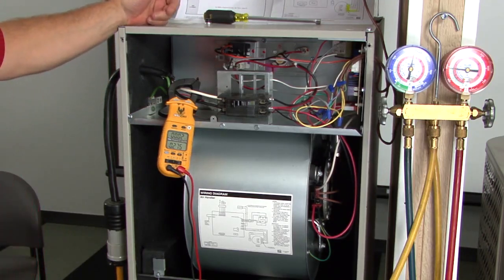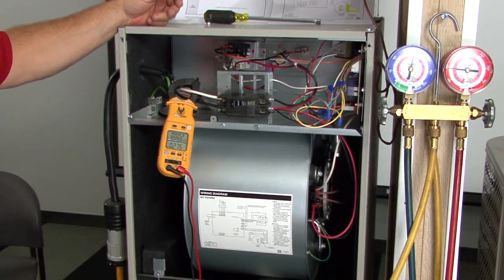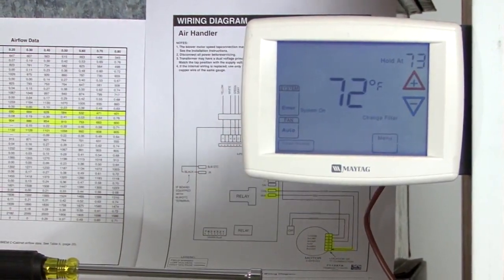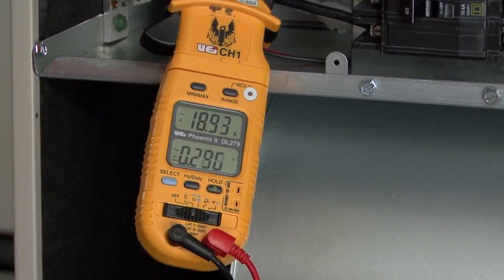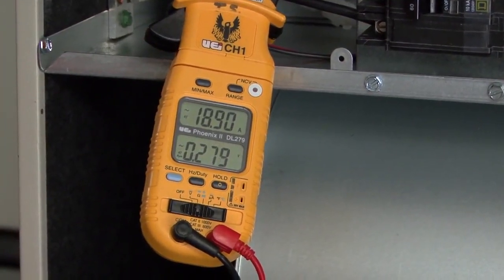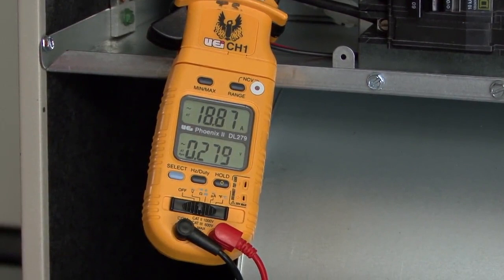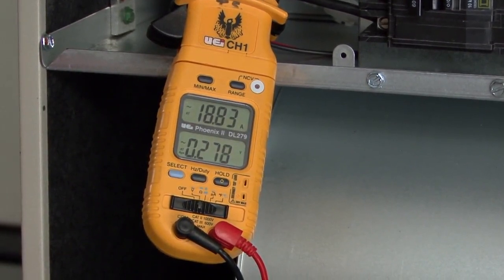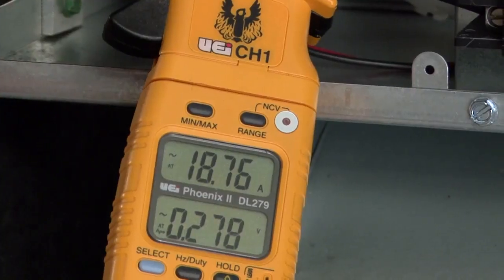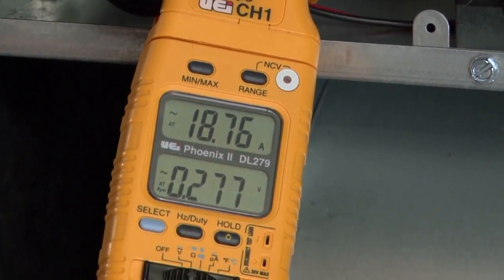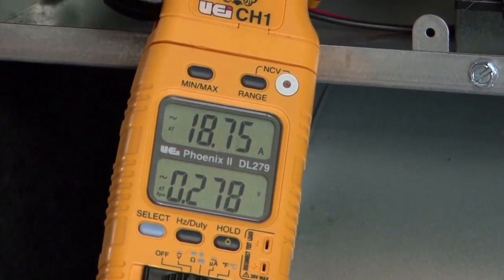So this one here, I've already got an amp probe on the power line coming in. We're going to turn it on. I got the thermostat set to emergency heat, and as you can see from the meter here, 5 kW, we're pulling about 19 amps. That's about right. You're going to pull about 20 amps for each element that you have inside that heater kit. Like I said, it depends on the exact kW, and also depends on the voltage. So on this, the amp draw is a little bit lower because we got a lower voltage.